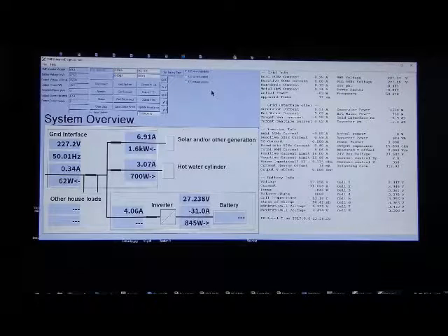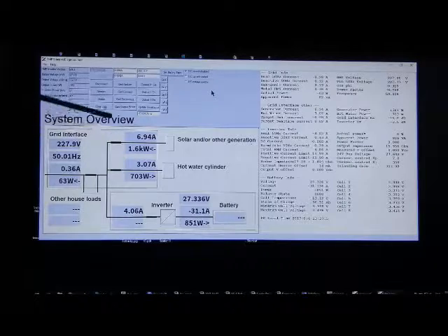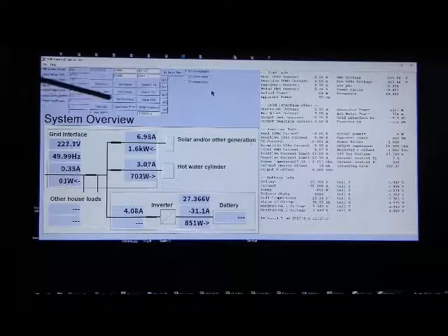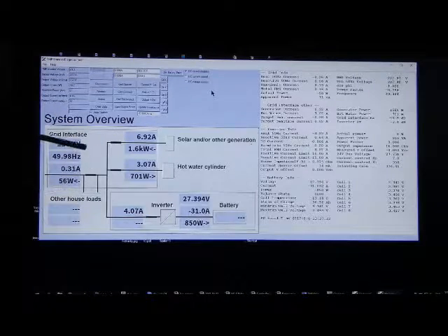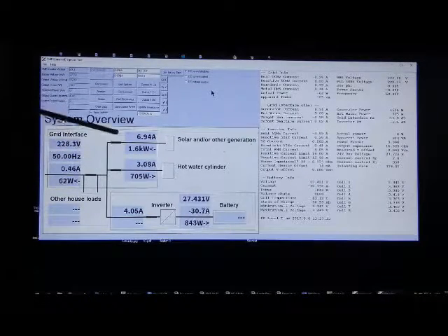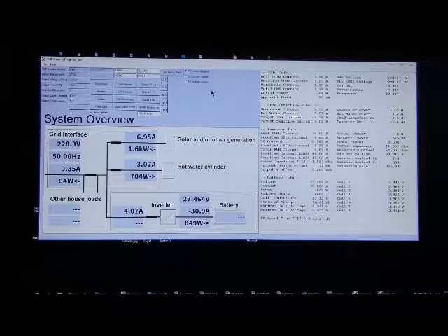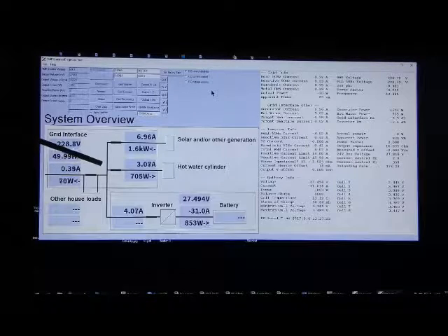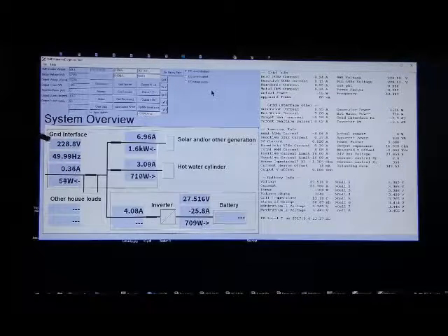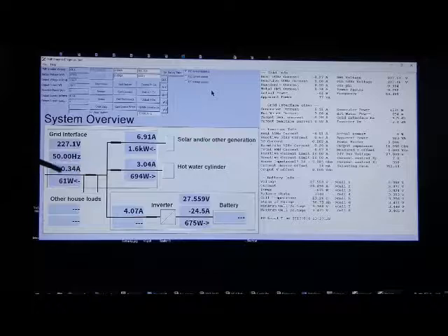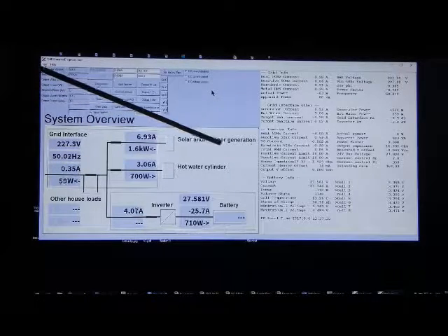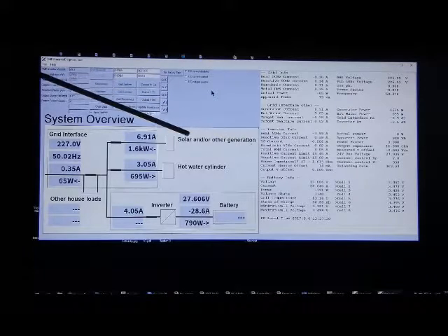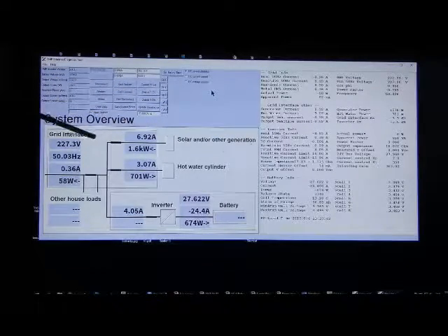This is our control and monitoring program for the system. We have here a system overview. You can see the various currents and powers being measured in the system. This is a development tool, so we want a nice fast response so we can see things happening. So these figures haven't been filtered very much and they jump around a little bit. So here we have a grid connection coming in, and we have the grid voltage currently 228 volts and the frequency 49.99 Hertz, and also the current coming into the house. Here we have the solar array, and that currently is putting 1.6 kilowatts into the house.